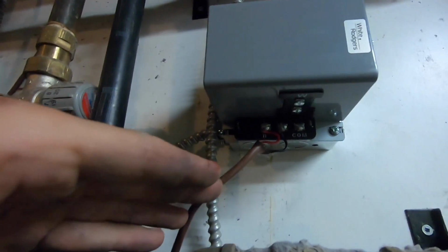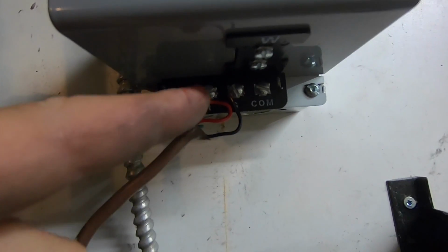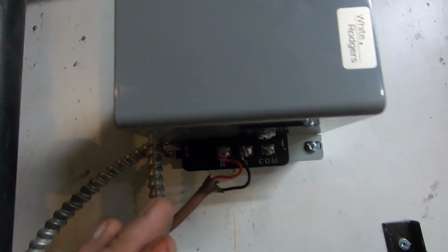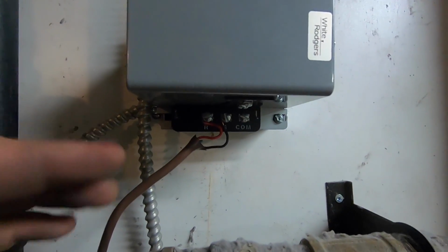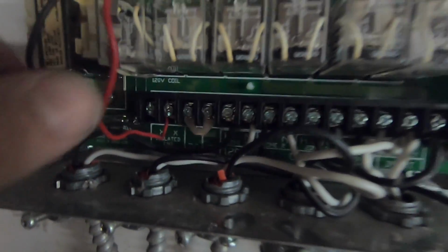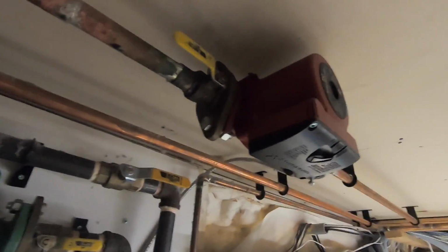Alright guys, so there you have it. So technically if you short out the R and G, this pump will go on. So right now it's calling, so this pump is only going to go on when this is made. Before it was running all the time. See my wire here? That's my call to the end switch. So when this makes, this pump goes on.